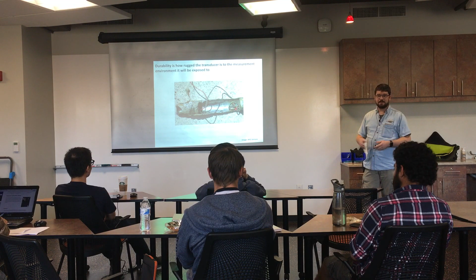Another thing to consider, which you won't see on the data sheet, is the signal conditioning. This impacts the cost to use the transducer. Say we're using thermistors to measure temperature: the sensor itself is very cheap, much cheaper than something like an RTD, but the signal conditioning for it is more expensive. So you have to do a trade-off analysis: how many sensors am I going to use? Does it pay to buy a couple that have everything integrated, or buy lots of sensors plus some expensive signal conditioning hardware to go with them?